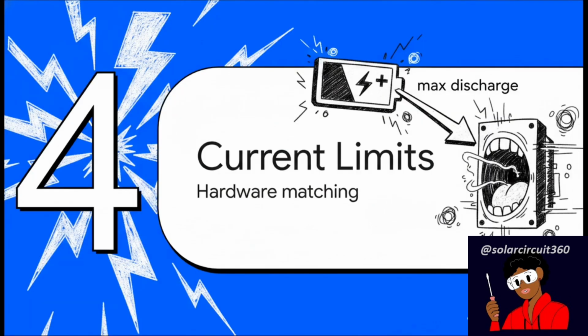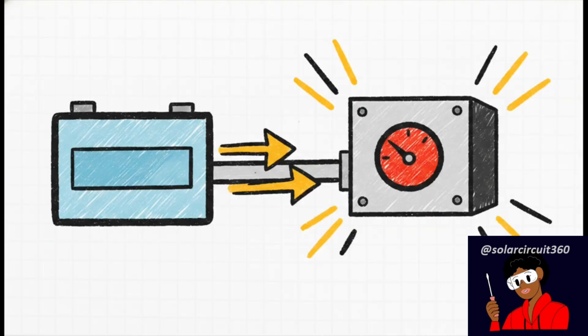Okay, Section 4, current matching hardware limits. Let's talk current. The absolute most common mistake here is just maxing out the discharge values simply because you've got a thirsty inverter to feed. To grasp why maxing out those current limits is a terrible idea, we have to look at this fundamental equation. Power equals voltage times current. This tells us exactly how much energy your inverter is demanding from your battery. When your inverter's power demand goes up, the battery current has to step up to deliver it.